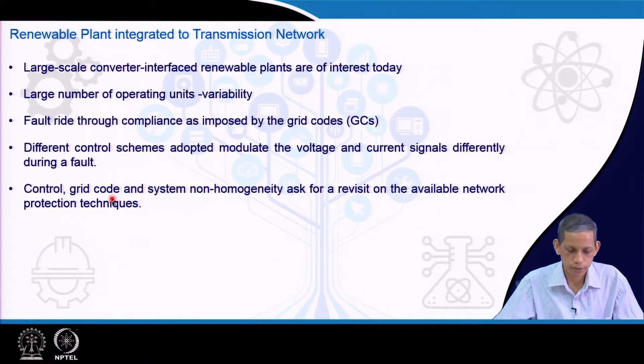Let us come to a large scale renewable plant, where we have several such units depending upon the capacity of each PV plant and its associated inverter, and then the aggregation of that leads to a step up transformer. Such units, in multiple numbers, are connected to a common collector bus, and then this large scale integration is connected to a high voltage bus through another main step up transformer. A typical example will be having 0.48 kV to 33 kV at the first level and from 33 kV to 220 kV or 400 kV at the next level.